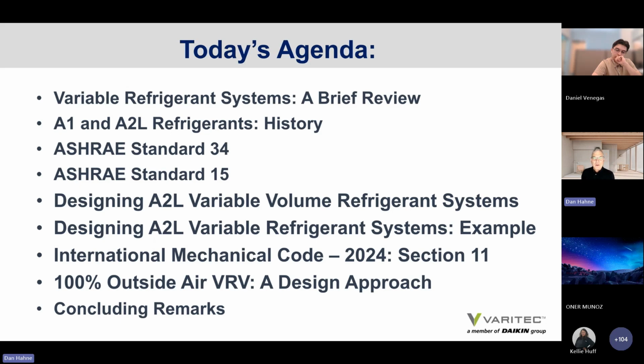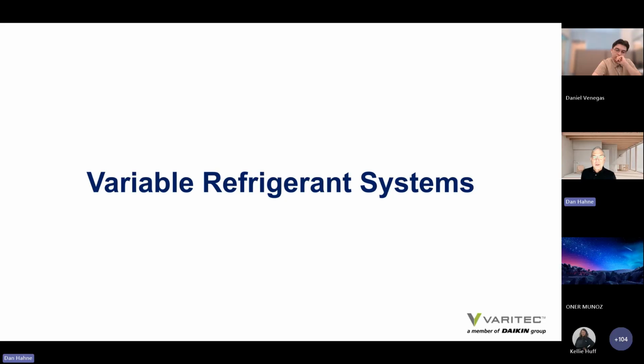Then we're going to go through a very simple office example to show how to calculate releasable refrigerant charges to a space and see whether or not that space is in compliance with Standard 15 and the refrigerant concentration levels the standard calls out. Then we're going to look at some of the language in Section 11 of the International Mechanical Code 2024, and then a design suggestion to help mitigate refrigerant volume within a building by using a decoupled 100% outside air variable refrigerant system. And if time permits, perhaps some concluding remarks.